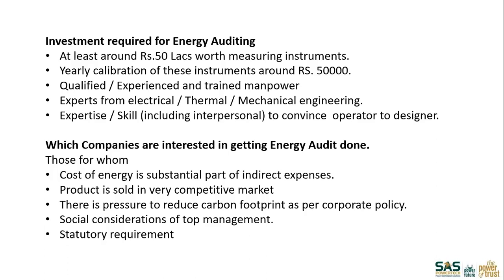Because as I had told a few slides before, you have to believe in measurements. Unless and until you measure, you cannot control. That's a truth. So you have to invest a lot in measuring instruments. Then yearly calibration of these instruments will also cost around 50,000 rupees, because all the equipment which you use for auditing has to be calibrated every year, because unless their readings are correct, your conclusions also will not be correct if the equipment do not measure correctly.